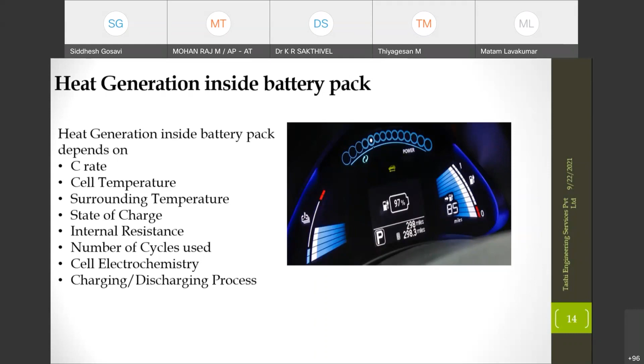So here is the design process that's followed. As I said, one of the foremost factors I need to know is the heat generation value. To arrive at this value, there are two methods: simulation and experimental based methods. We proceed with both methods in parallel. Once we get a value - say my rated heat load is 1000 watts, my peak load is 3000 watts - then the subsystem component design like the condenser, evaporator, system integration, ducting, the PHEV heat exchanger, all this component design starts once I'm able to get the value of thermal load.